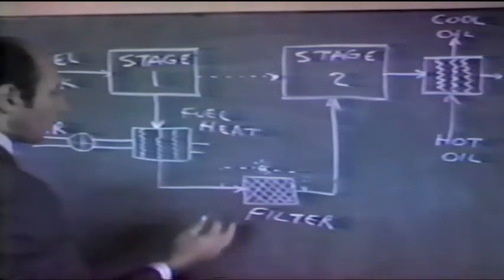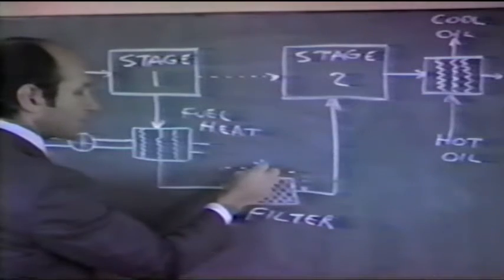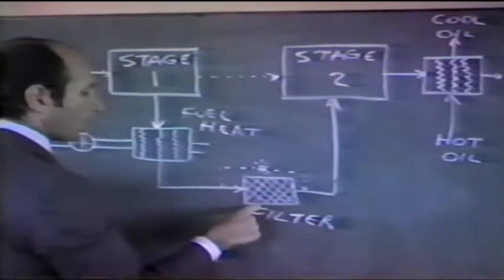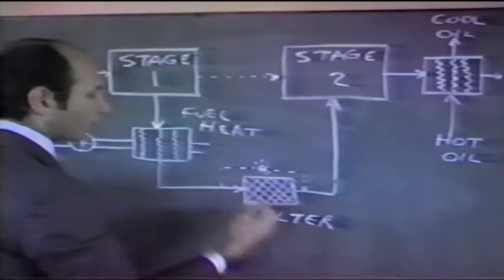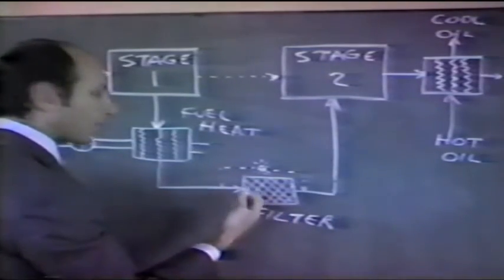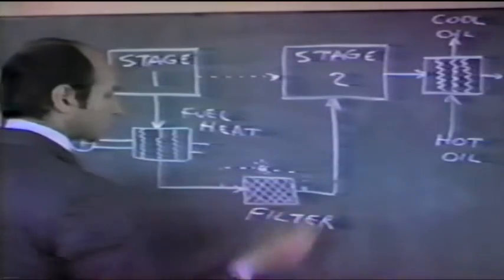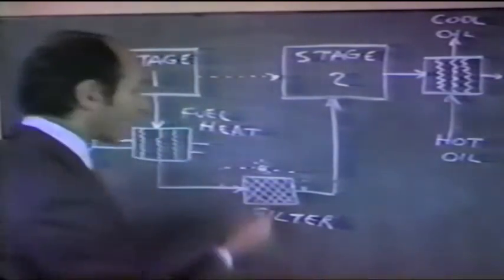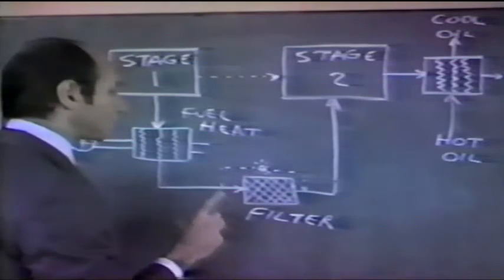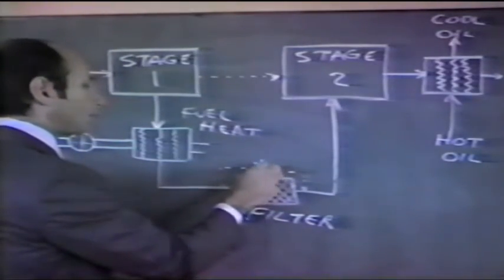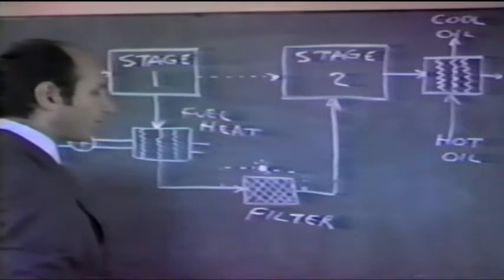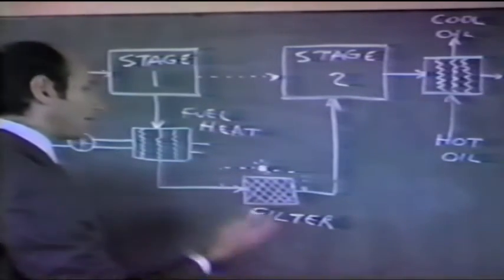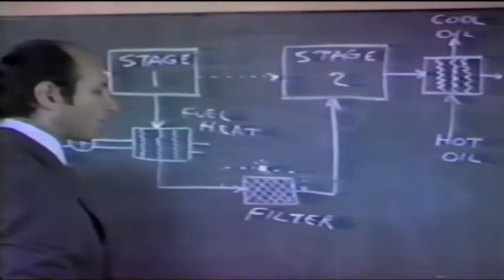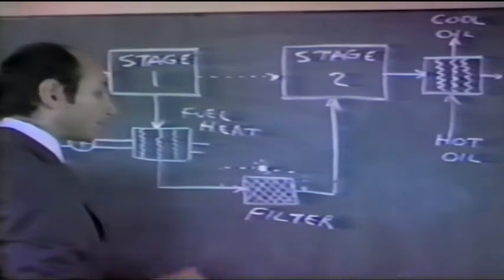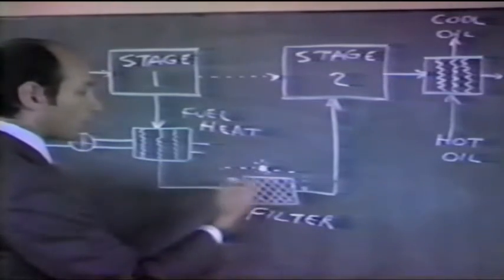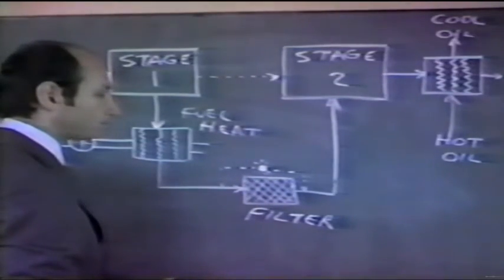Why would we do this? We would do this if we had an icing light, which would be caused by a bypass of the fuel filter, meaning the fuel filter is probably clogged with ice crystals. What would happen if the fuel filter was clogged because of contamination? That's right, we'd get an amber light also. So one of the things we want to check before turning on fuel heat is the fuel tank temperature, to see if it's cold enough for this to possibly be icing, or if it's a very warm fuel tank temperature, in which case we know for sure it's contamination.